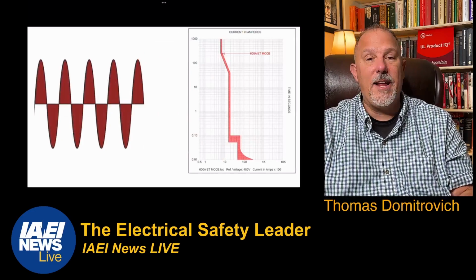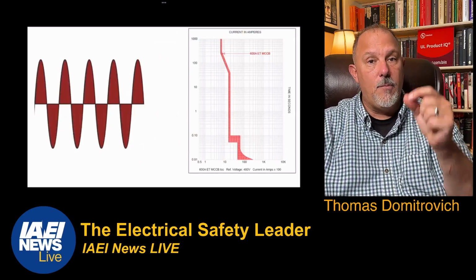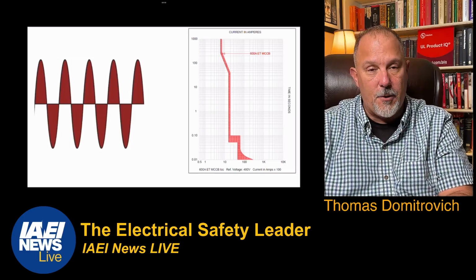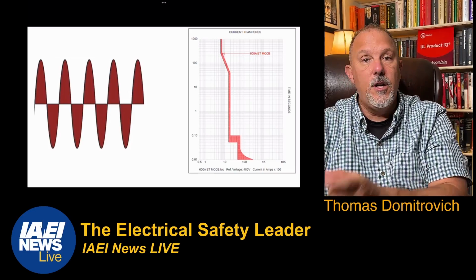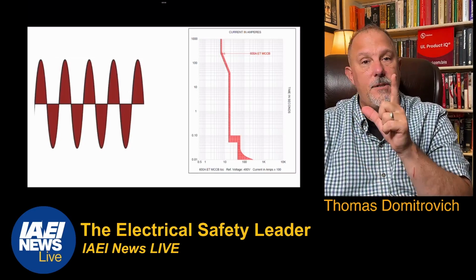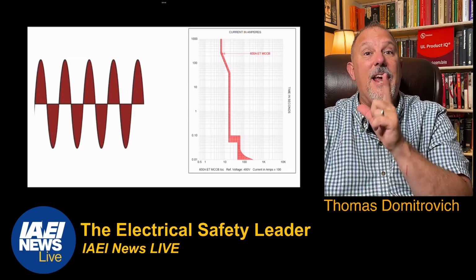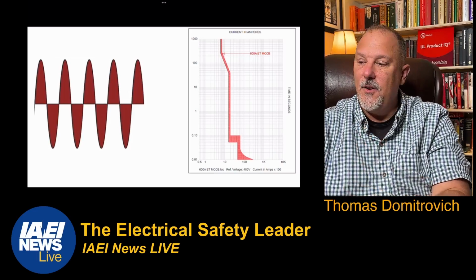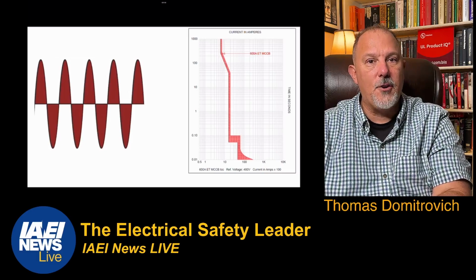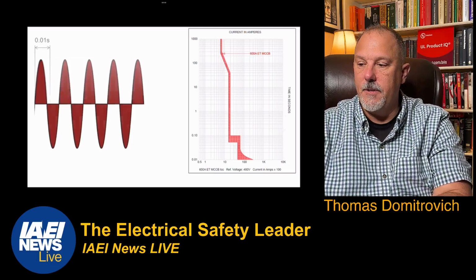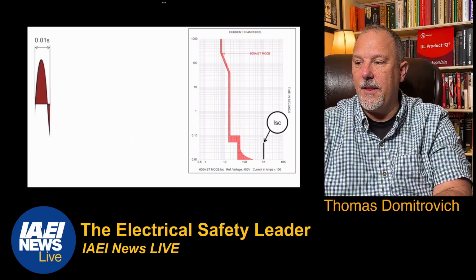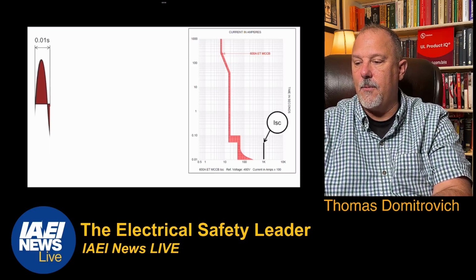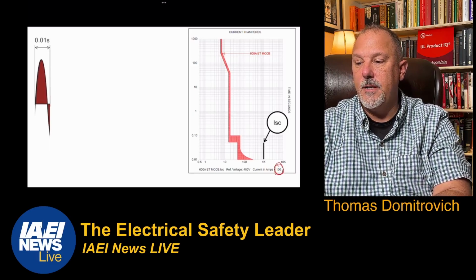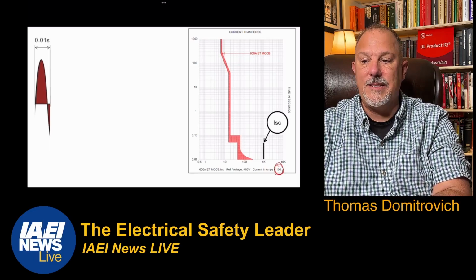So if I look at a 600 amp, what I'm going to do here is compare a 600 amp molded case circuit breaker versus an insulated case circuit breaker versus a power circuit breaker. All 600 amps. They're all the same circuit breaker ampere rating. But their trip curves, their time current characteristic curves will be different. So if I have a short circuit for this device at around 100 amps, and this is again current times 100, so that's 10,000 amps of fault current, I will trip in 0.01 seconds.